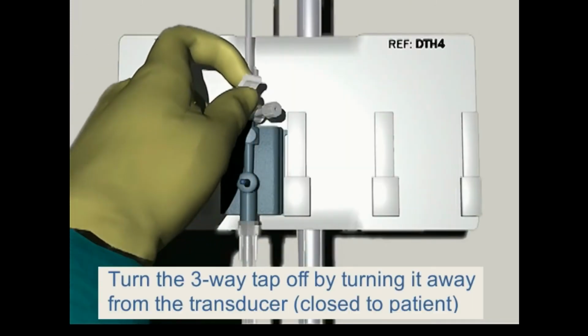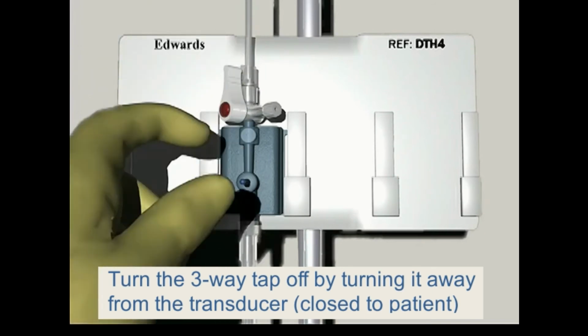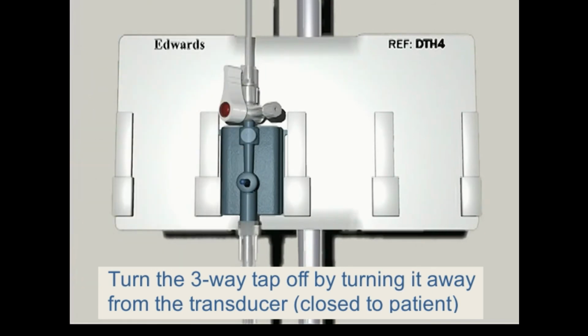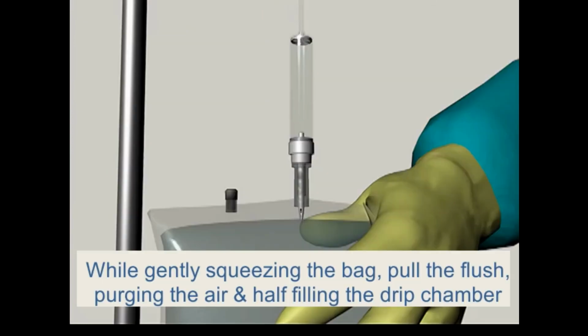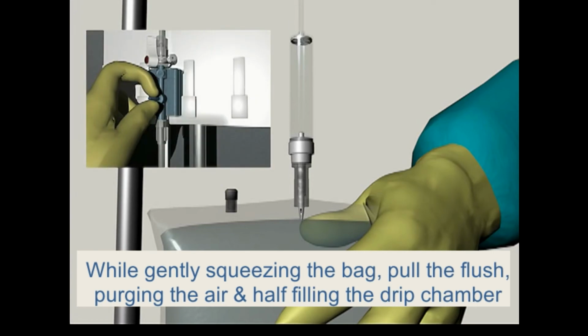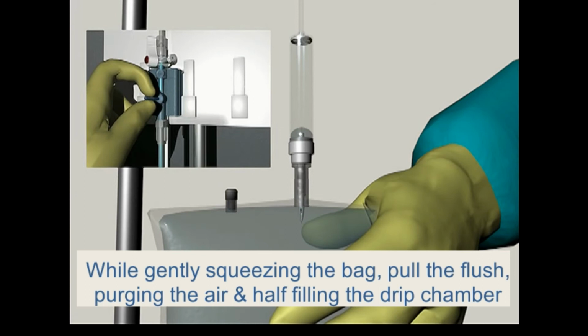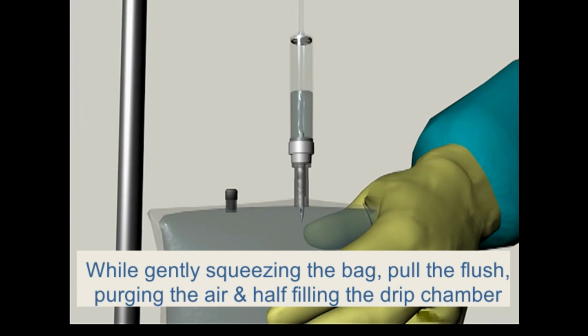Open the vent port by turning the stopcock toward the patient's pressure tubing and away from the transducer while leaving the vented cap in place. While keeping the IV bag inverted, gently squeeze air out of the bag with one hand while pulling the snap tab flush device with the other hand until air is emptied from the IV bag and the drip chamber is filled at least halfway, per institutional policy.